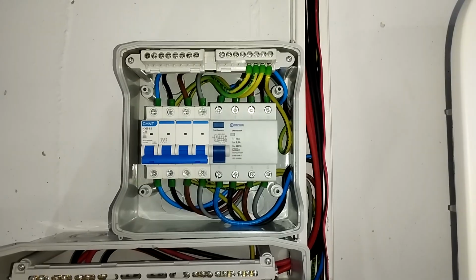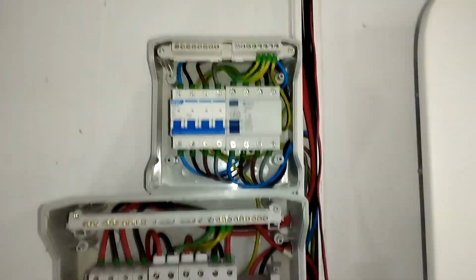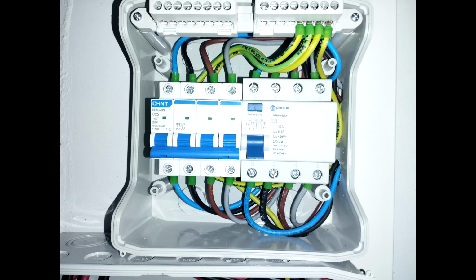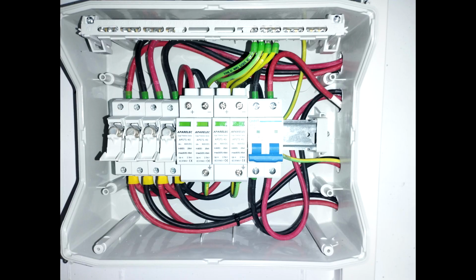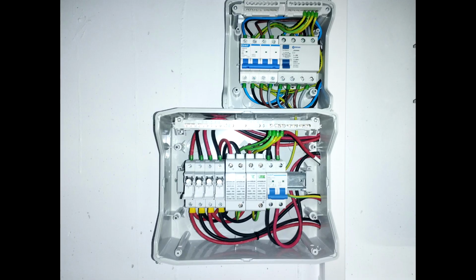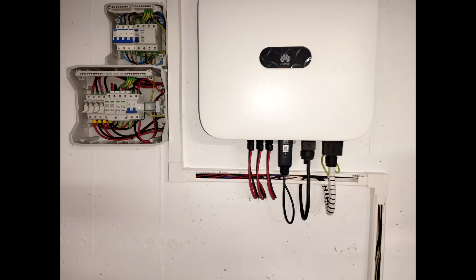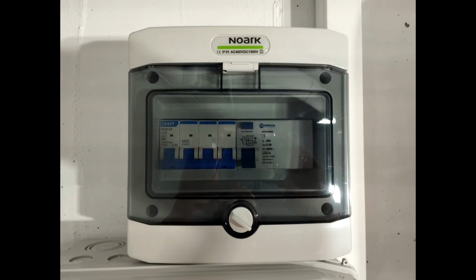You can see two protection enclosures, one for DC protection and one for AC protection. Strictly speaking, neither the low voltage regulations nor the manufacturer's manuals require AC and DC components to be placed in separate enclosures. It would be enough to keep them separated by a divider inside one enclosure with correct labeling and electrical isolation. But our company's standards, and more importantly, our personal standards, are higher than the minimum requirements. Therefore, we install AC and DC protection in separate enclosures and label everything clearly.